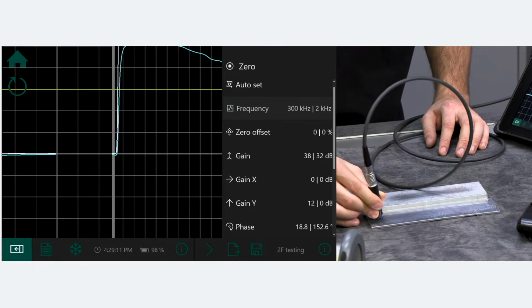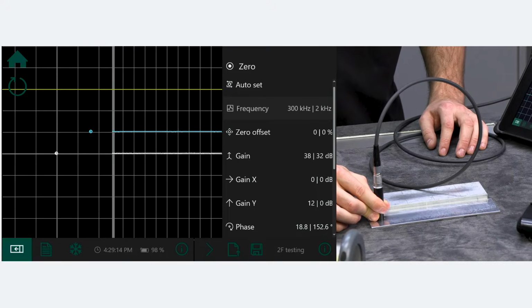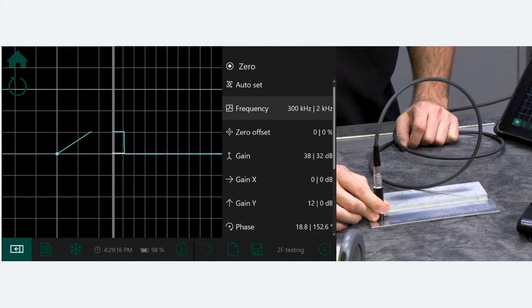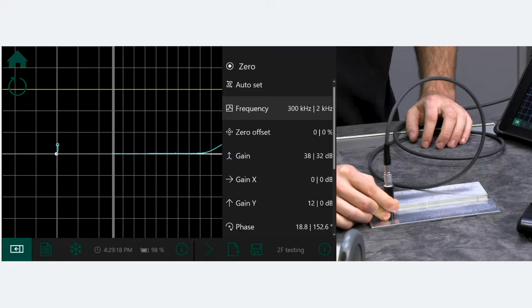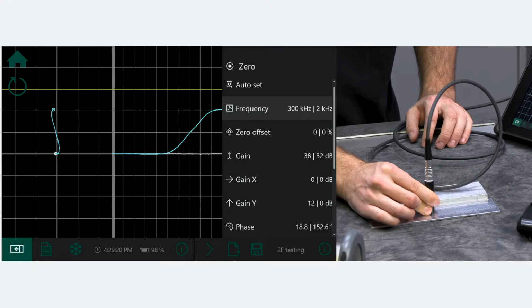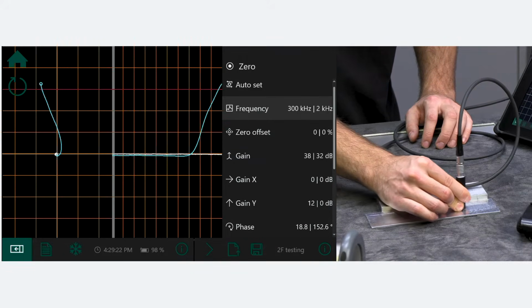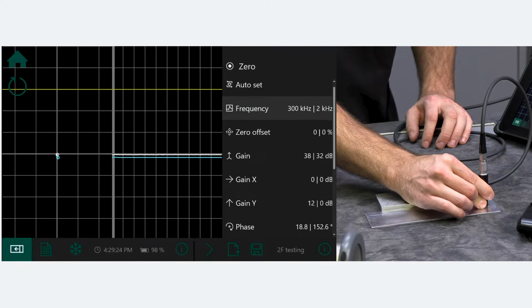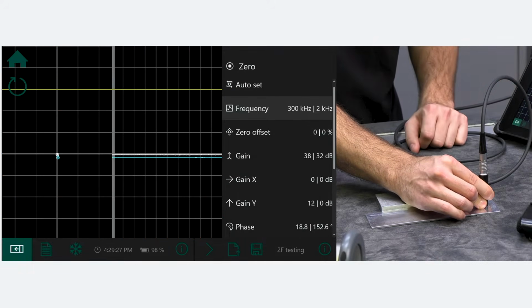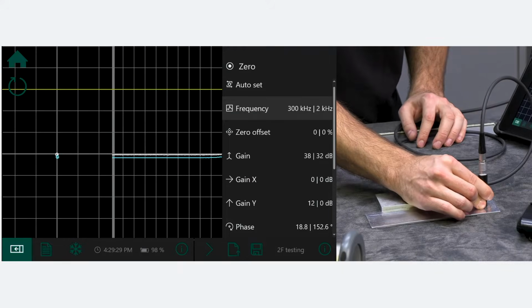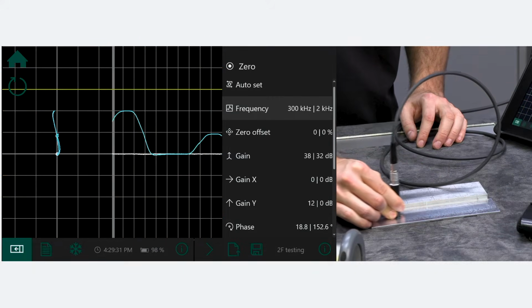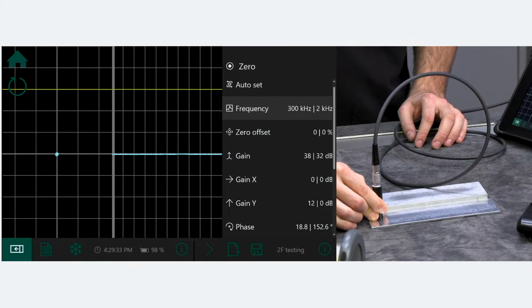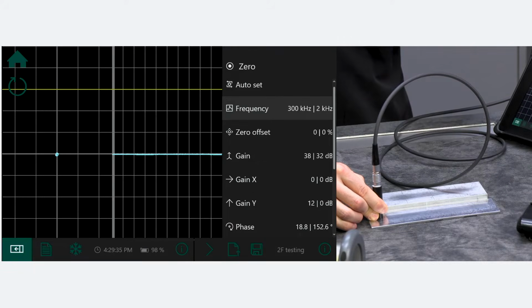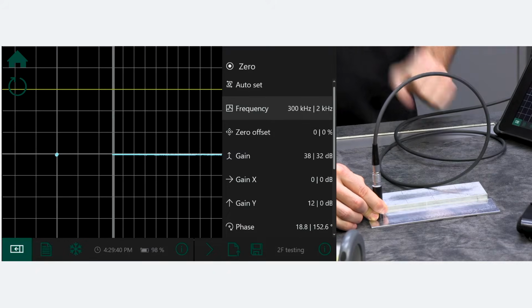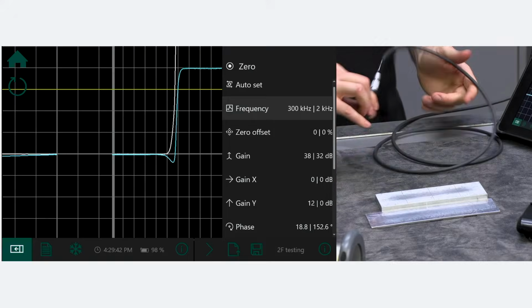If we do the same on the residual wall standard material, because this material is a bit different, we scan and we see only the blue signal is moving. So we know, okay, there we have a residual wall loss. The second frequency we use is 2 kilohertz. And we can really make a test in parallel for cracks and residual wall, and also decide, okay, this was a crack and this was a residual wall loss.